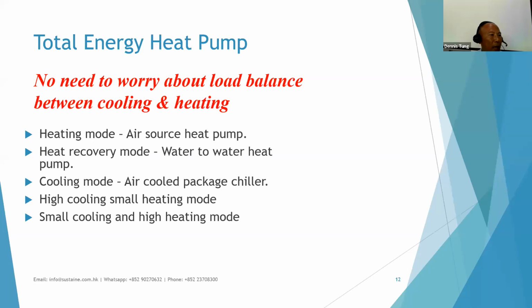Therefore, we have a total energy heat pump, which combines the two functions of an air source heat pump and a water-to-water heat pump. It can control by itself and modulate the amount of energy used to meet the demand of hot water and also for the cold chilled water air conditioning system. So this can help us reduce our effort to manually switch over the systems for better performance.